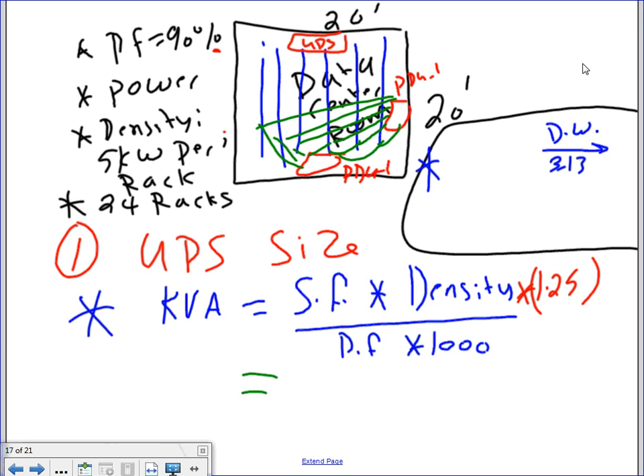One more time. I have a room, 20 by 20, and lately they size by racks, guys. You can size it two ways, either by racks or by square foot. For the square foot, we did one. We're going to do the second one for racks. So please write down another formula. Instead of square foot, I'm going to say number of racks. Write the little formula: number of racks multiplied by the density multiplied by the loss factor divided by the power factor.